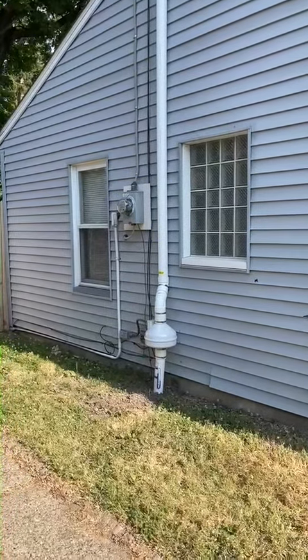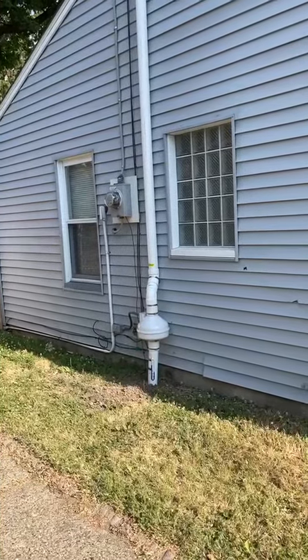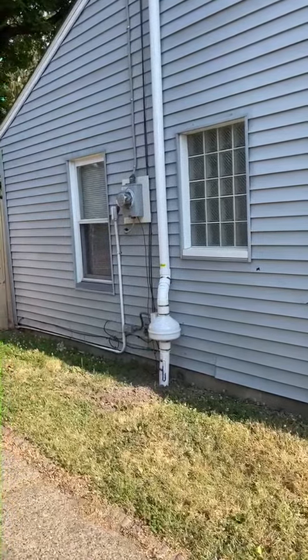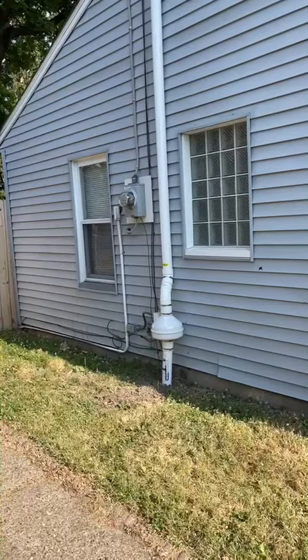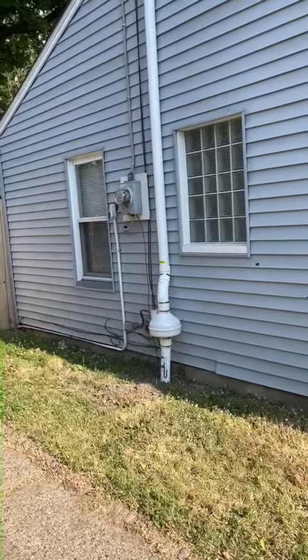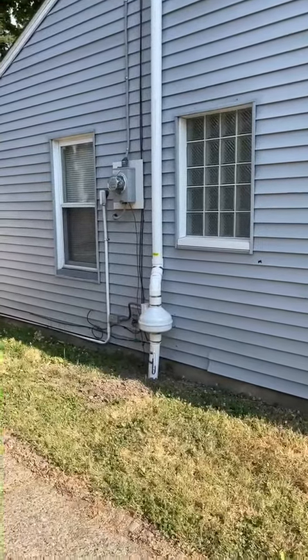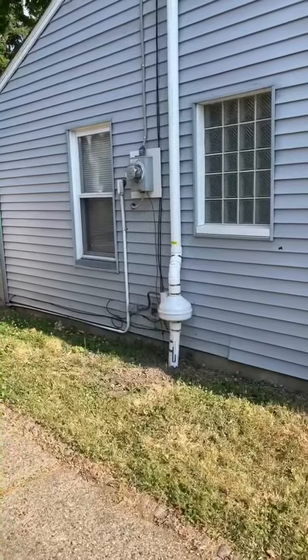We're out here in Akron today picking up a post-test Radon Mitigation. They tested above 4.0. With that mitigation system installed, we were able to drop that level down to 0.3. So again, a nice, awesome mitigation job here at Radon Eliminator. Let me walk you guys through this one a little bit because it is a little bit different. You've seen this once on the channel before.